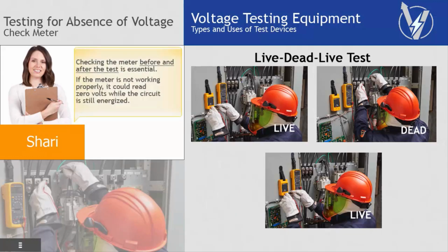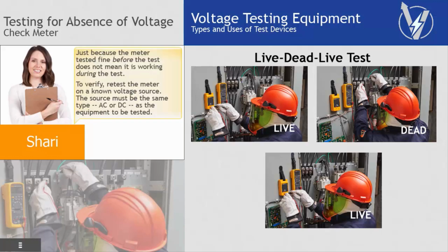Checking the meter before and after the test is essential. If the meter is not working properly, it could read 0 volts while the circuit is still energized. Just because the meter tested fine before the test does not mean it is working during the test. To verify, retest the meter on a known voltage source. The source must be the same type, AC or DC, as the equipment to be tested.